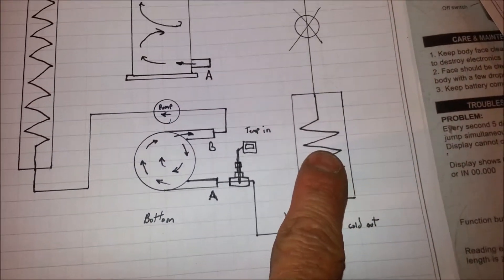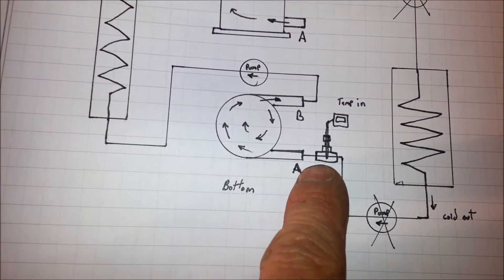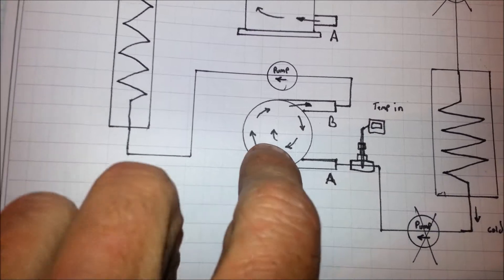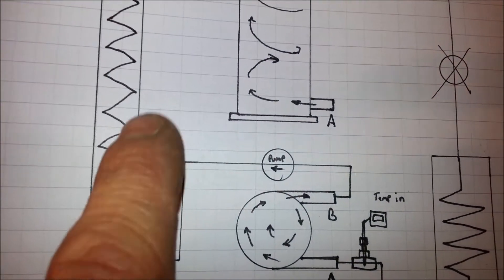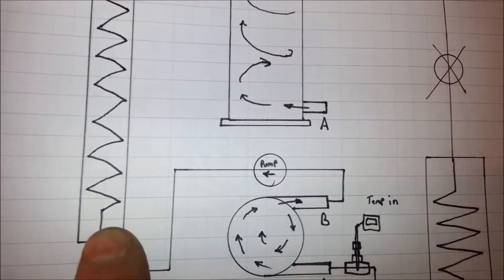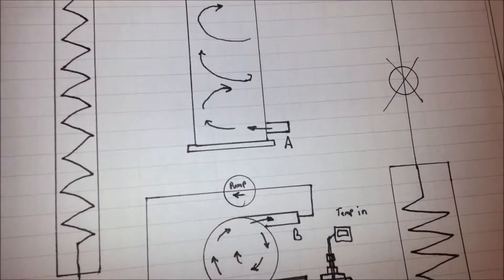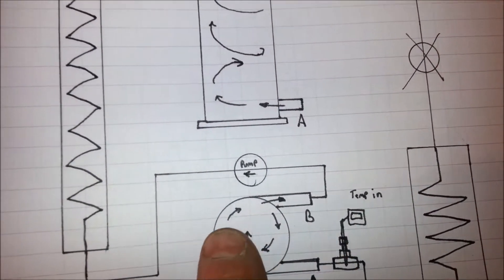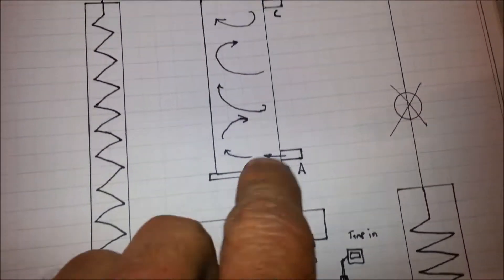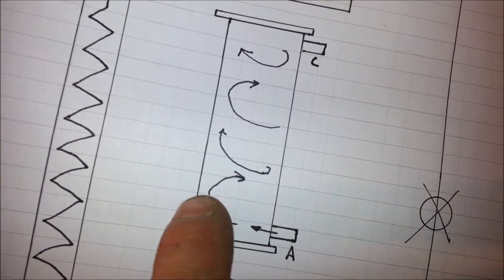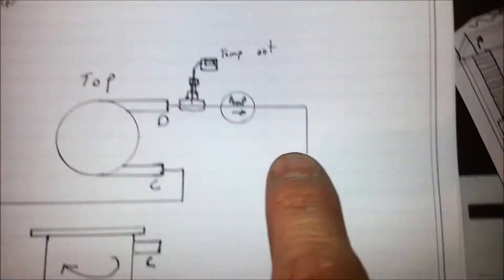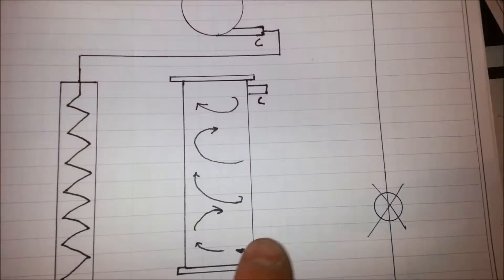The cold discharge from the radiator in the house is pumped into the bottom of the pipe, where most of it is sucked up by the heating element intake. Whatever is not sucked up by the flow discrepancy, which is shown another way here, simply travels up the pipe and is sucked back in here at D, where it is pumped into the radiator. So there's sort of a mixing effect that would take place here.